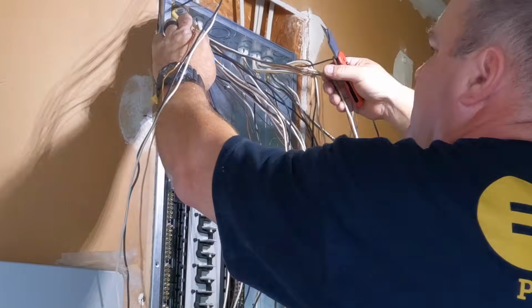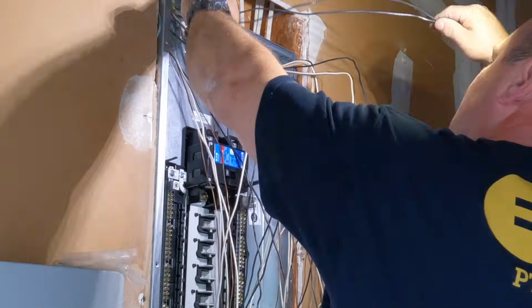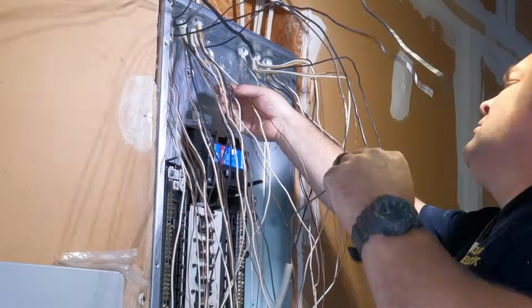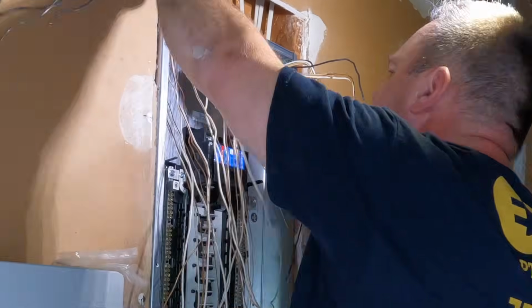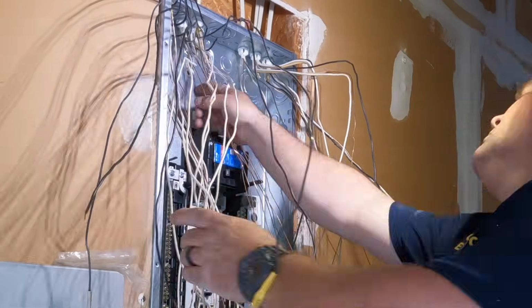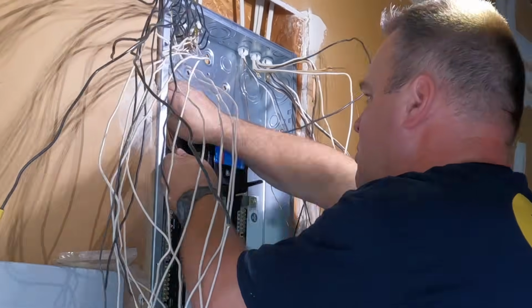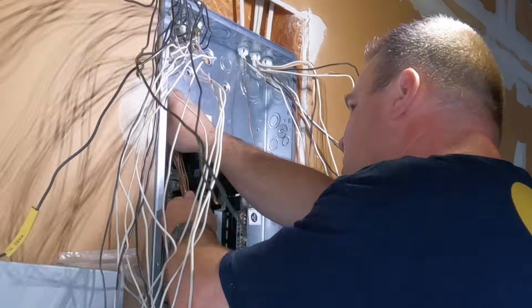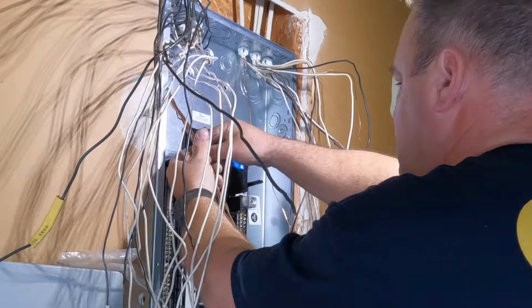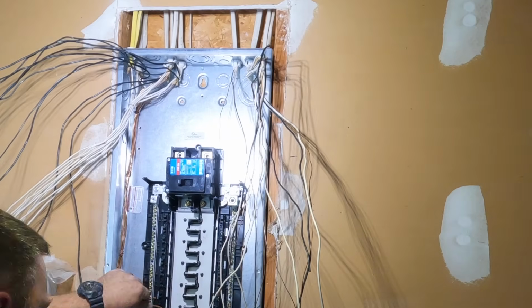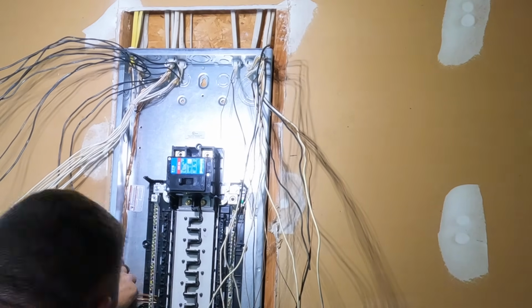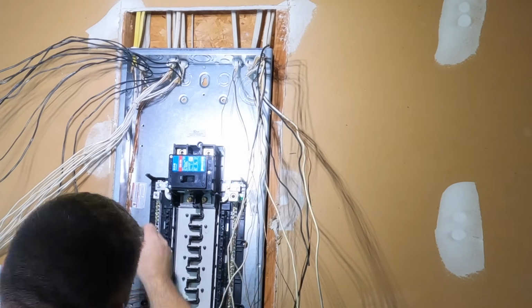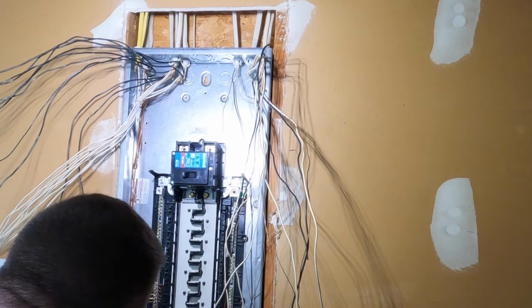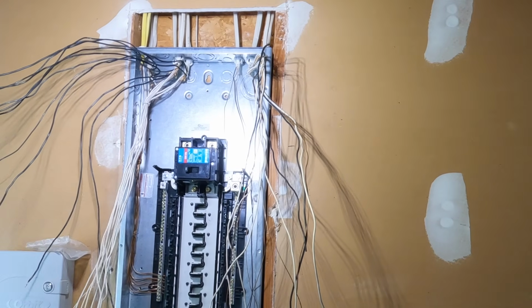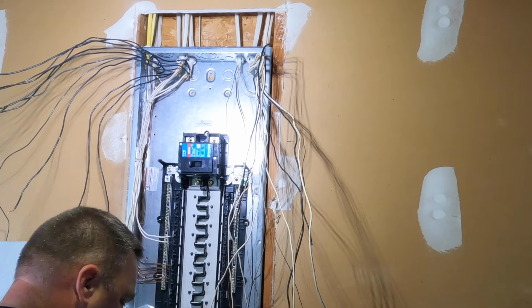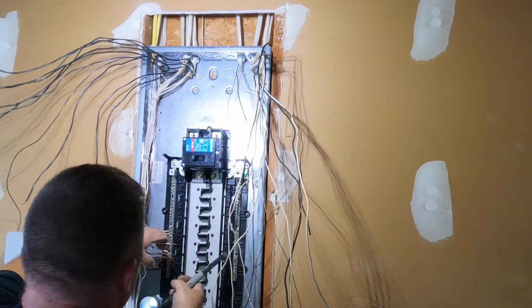The grounds and the neutrals go to the same exact terminal inside a main breaker panel. This panel is the main breaker, main disconnect panel, so it has the main bonding jumper. That just connects the neutral from the service to the enclosure, and this is where your equipment grounding conductors begin. And the equipment grounding conductor is used to carry fault current to facilitate the circuit breaker, in layman's terms.